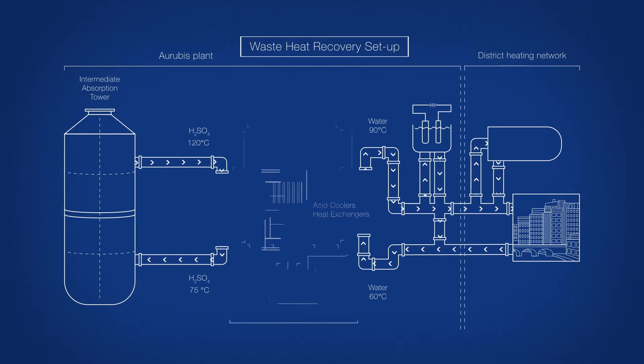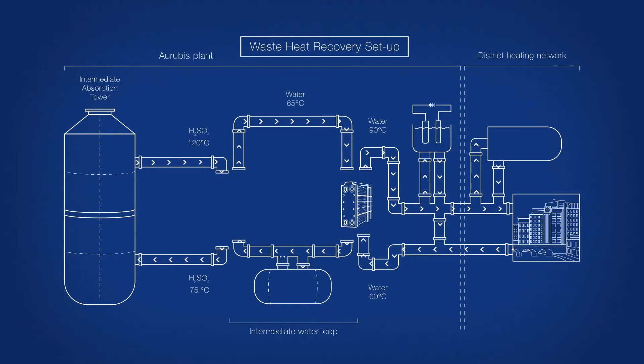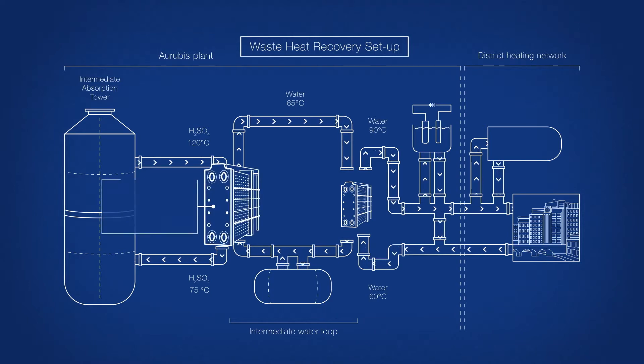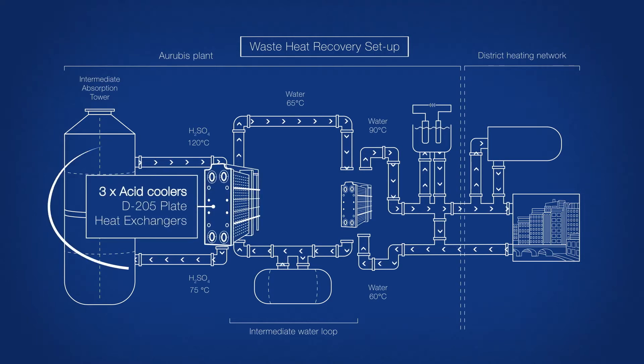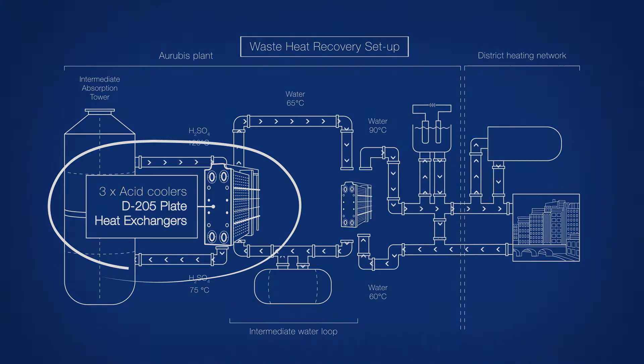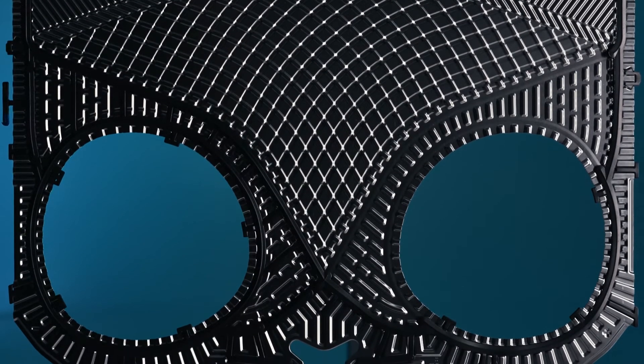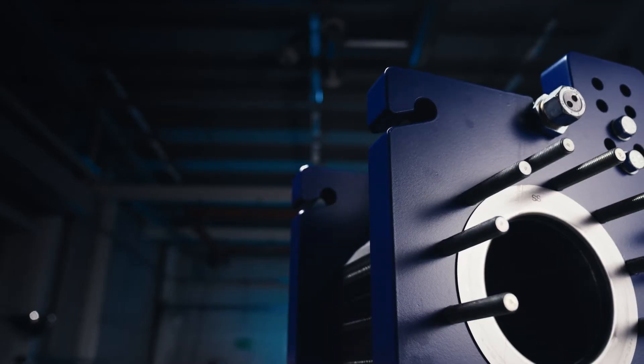However, this added further complications, since higher process temperature substantially increased the corrosiveness of the acid. To cope with the corrosive nature of the fluid, each of the sulfuric acid lines has three heat exchangers using unique Alfa Laval plates made of Hastelloy D205 material. This nickel-based alloy is resistant to concentrated sulfuric acid at high temperatures — a tried and tested solution with more than 300 units installed worldwide and decades of operation.